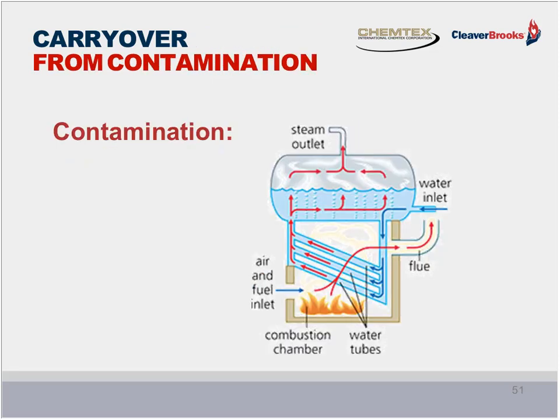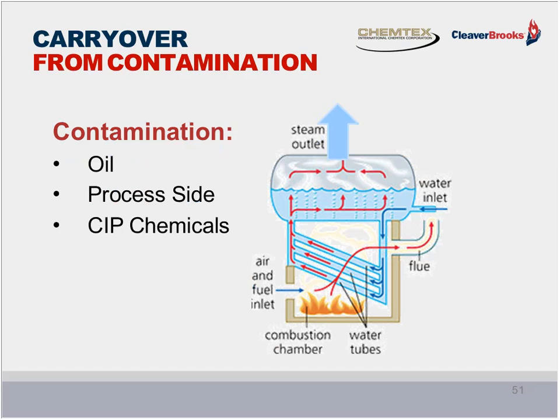The other source of potential for carryover is contamination. The contamination can come from oil. It can come from the process side. You could have something like milk coming back into the boiler, which is going to increase the suspended solids in the boiler and cause carryover.